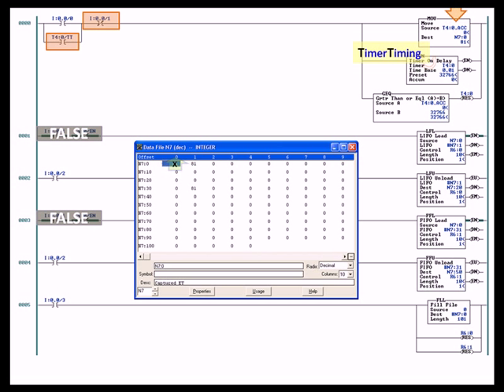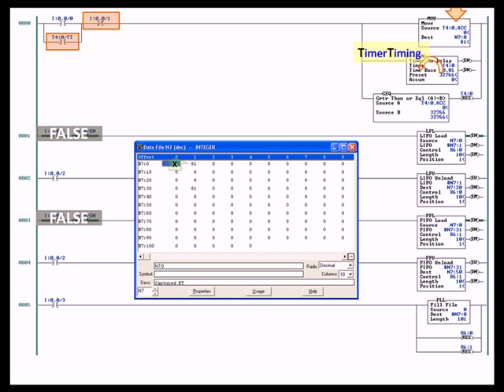The time base for this timer is 100th of a second, so every 100th of a second the preset, or I should say the accumulate, gets one closer to the preset. So every second the accumulate would increase by 100.